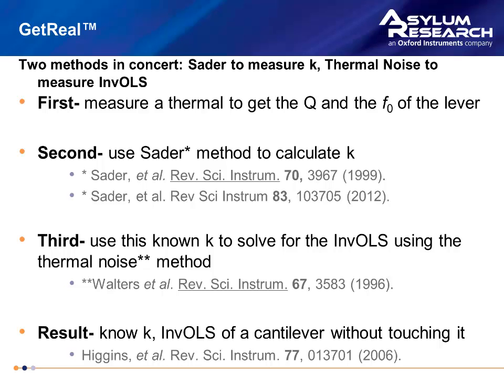After we get the spring constant, we'll use the thermal noise method to calculate the sensitivity, and this is a little different than how we usually use the thermal noise method. Normally, we'll take a known invols and then we measure the Q and the resonance frequency of the cantilever to calculate the unknown spring constant. With GetReal, we actually already know the spring constant, but we don't know the invols, so we just rearrange the thermal noise equation to solve for invols.